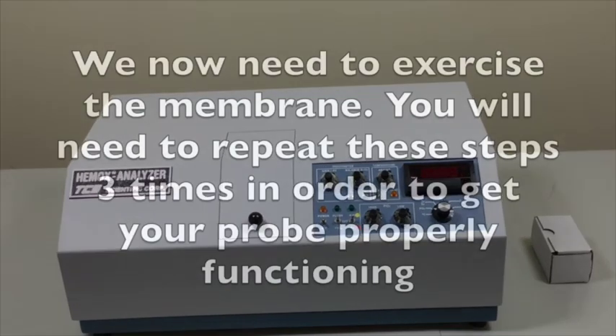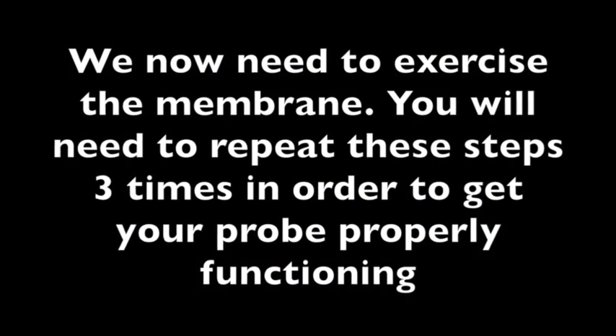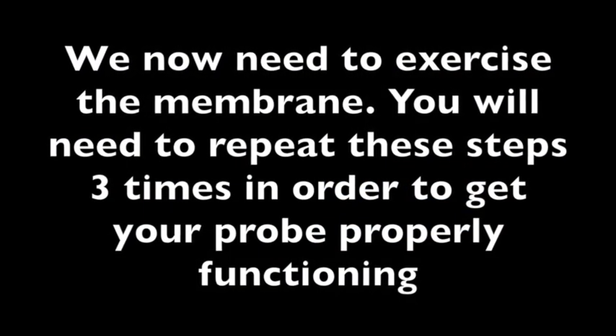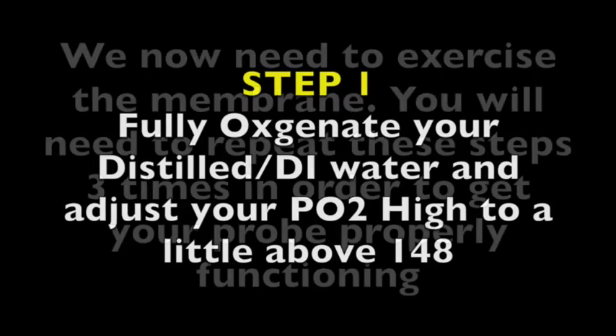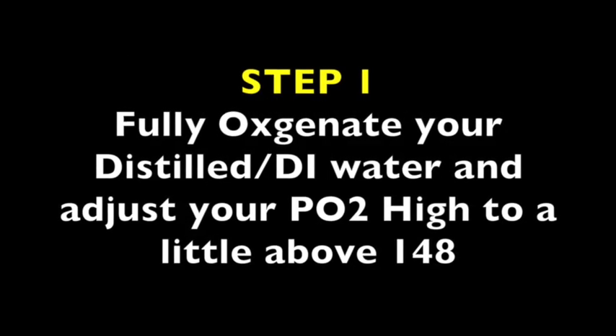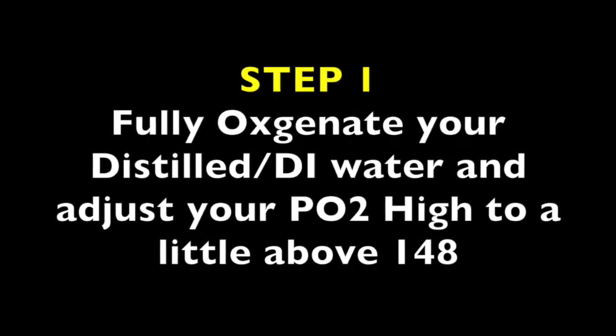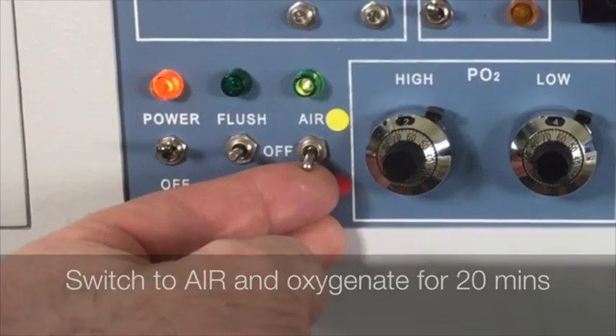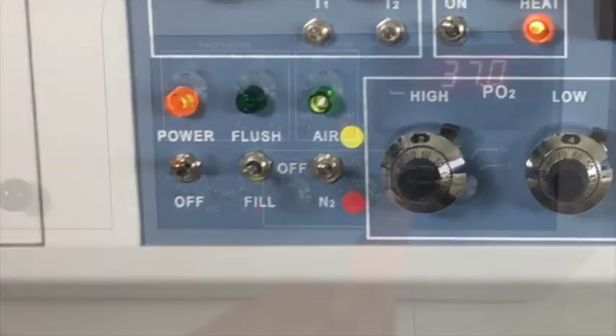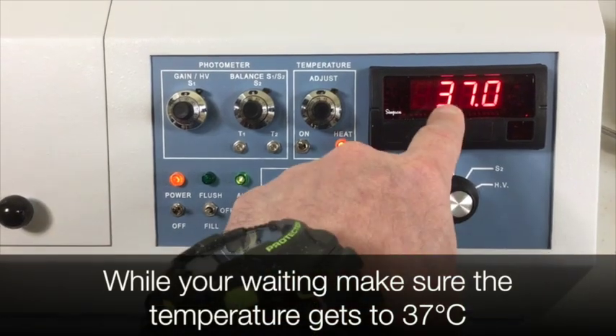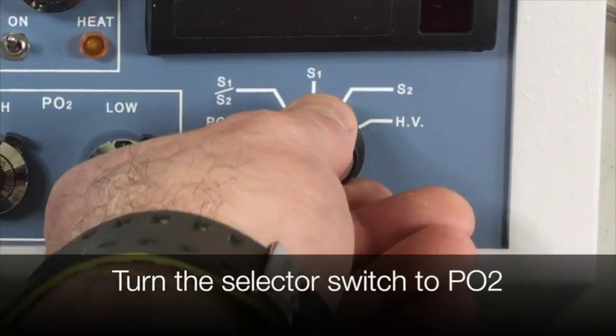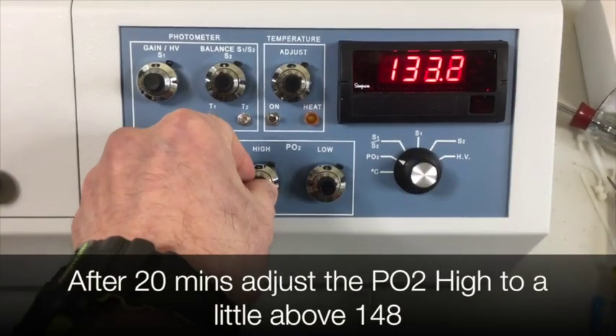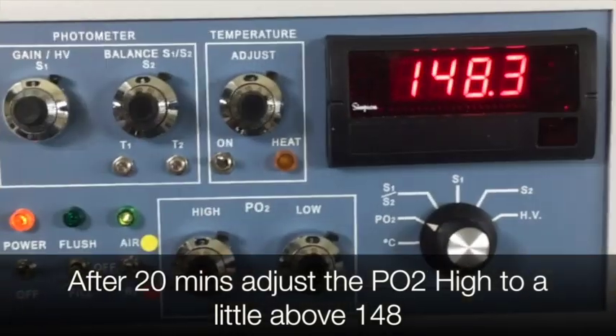Close lid. We now need to exercise the membrane. You will need to repeat these steps 3 times in order to get your probe to function properly. Step 1. Fully oxygenate your distilled or DI water and adjust your PO2 high to a little above 148. Switch to air and oxygenate for 20 minutes. While you're waiting, make sure the temperature gets to 37 degrees Celsius. Turn the selector switch to PO2. After 20 minutes, adjust the PO2 high to a little above 148.